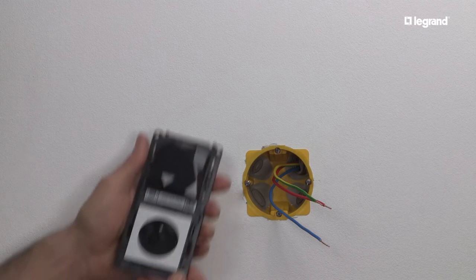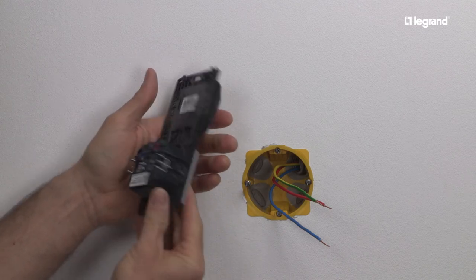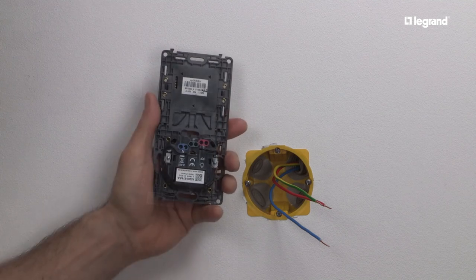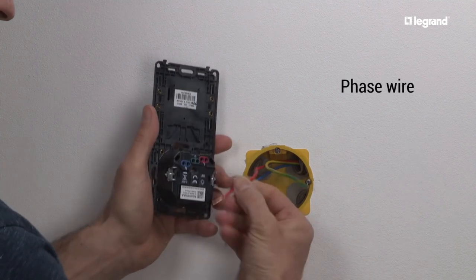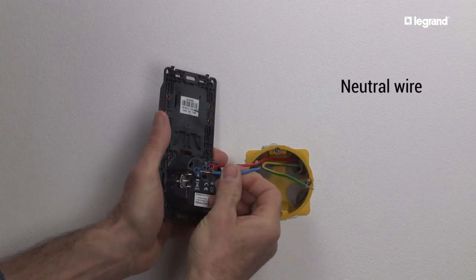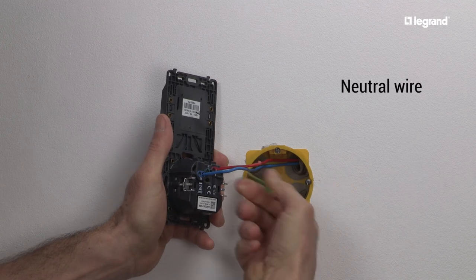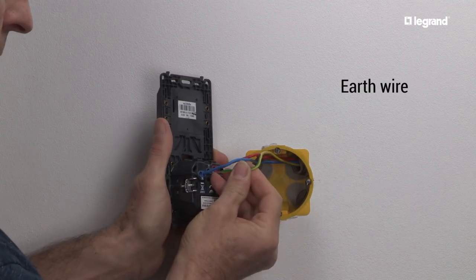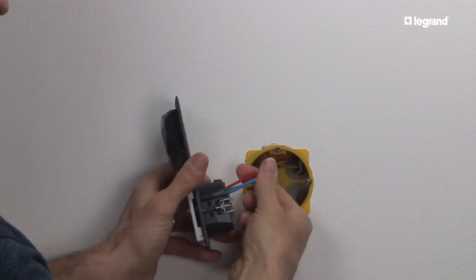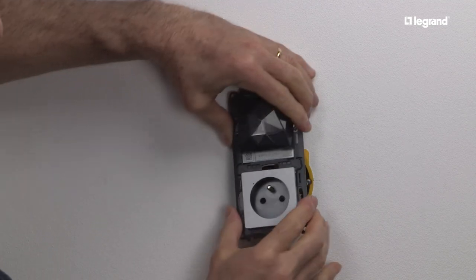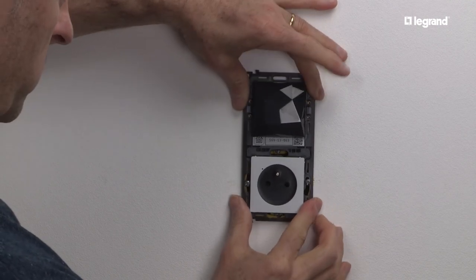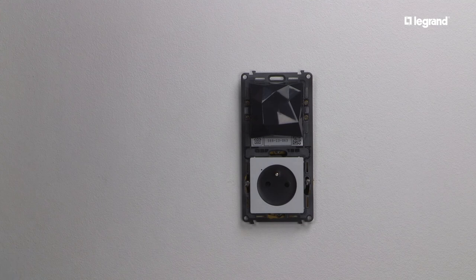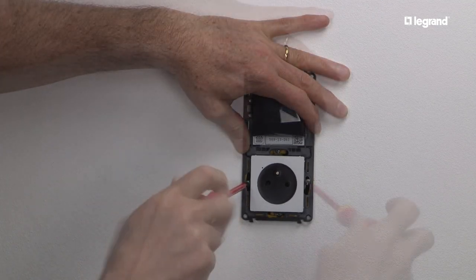The connected gateway power outlet is flush mounted in a 1-gang box 40mm deep. It can replace a conventional power outlet. Connect the wires to the automatic terminals: phase wire, neutral wire, and earth wire. Mount the gateway power outlet in its flush mounting box. It can be fixed with screws or with a clamp provided.